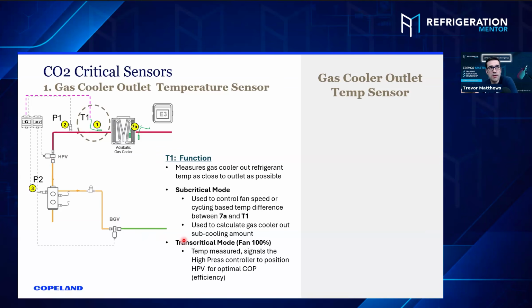And one of the things to remember is this is no different in HFC. When you're checking your subcooling, you check your pressure, your SCT, SDT, you convert it into temperature, then you get the outlet of the gas cooler to drop leg temperature, and then you do your subtraction, then you get your subcooling. This is what the controller is actually doing. It's just what we always did in a refrigeration system, but now the controller is monitoring that and manipulating the pressure to throw it into a subcooled state. So that's subcritical mode. So what else does T1 do?